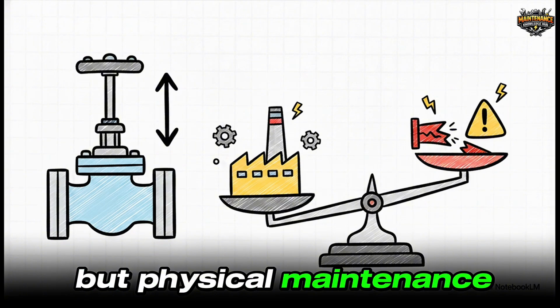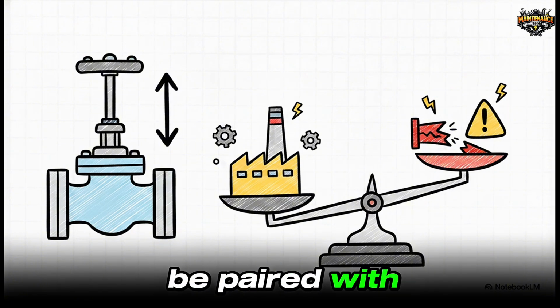But physical maintenance isn't enough. It has to be paired with calibration and stroke testing. This is the difference between a smoothly running plant and a catastrophic shutdown. You're commanding the valve across its full travel to make sure it moves smoothly without lagging.